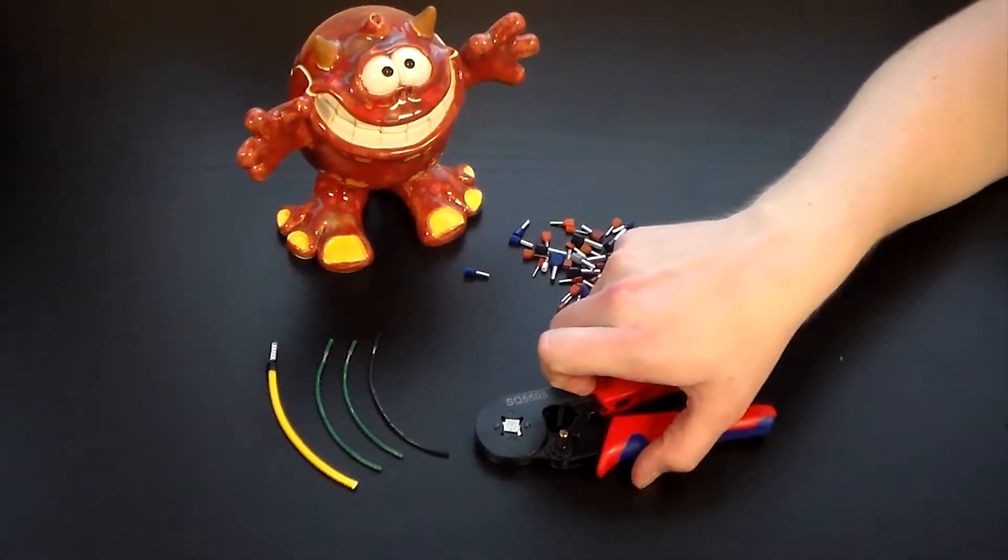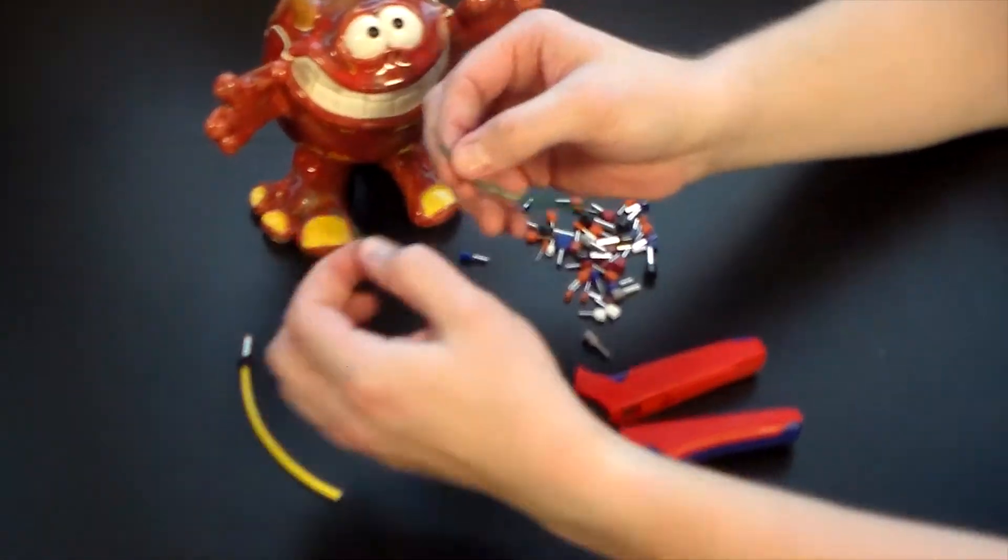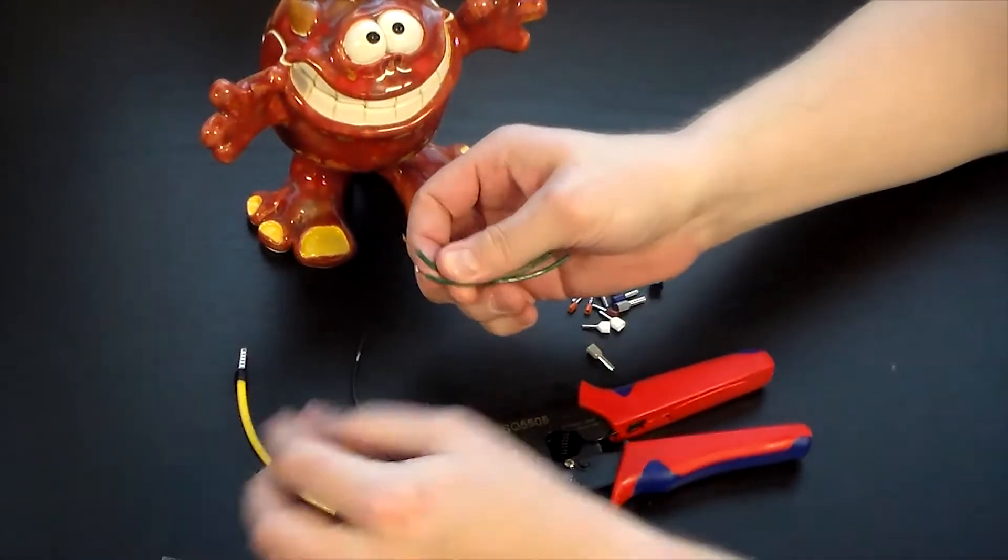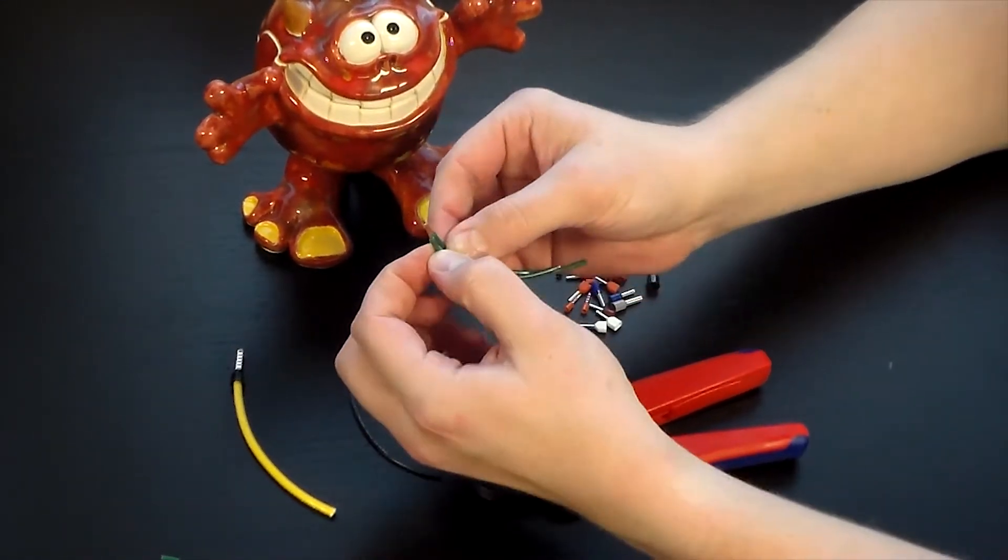It also does twin wire. Twin wire ferrules, it'll do 28-gauge to 14-gauge because the 14-gauge twins will be a larger diameter. So you want to go ahead and twist those together to make it a little easier to funnel them inside of the twin wire ferrule.